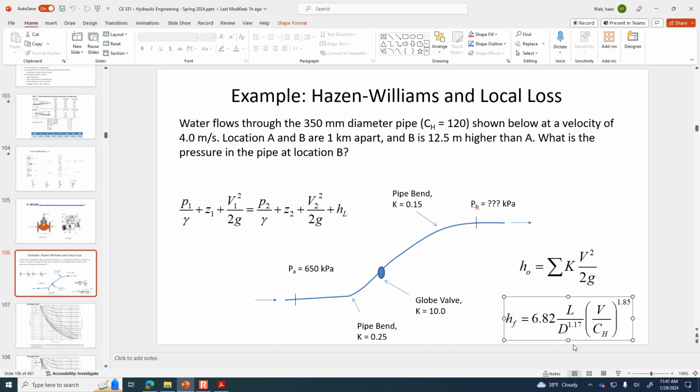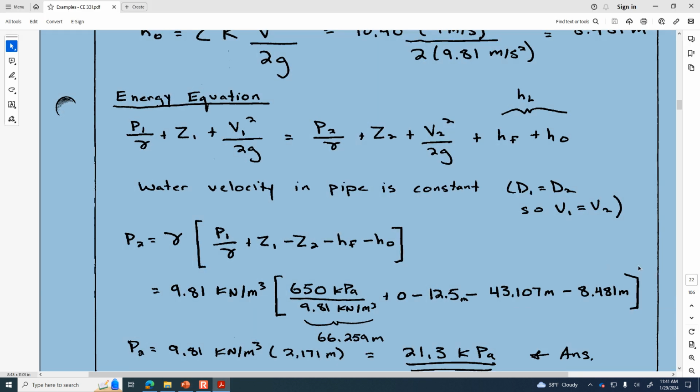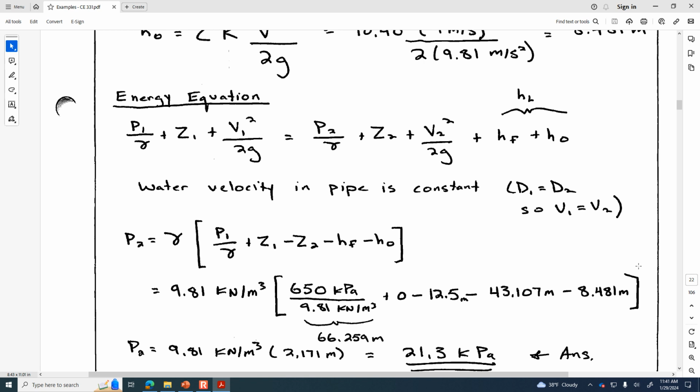If we have a larger diameter pipe, we're going to have a big reduction in the energy loss due to pipe friction. And as a plus, that larger diameter pipe would reduce the velocity head, and so the local losses would be smaller as well. So we could change in different fittings, and that maybe would help, but we'd have to know, well, how much extra pressure are we looking for?